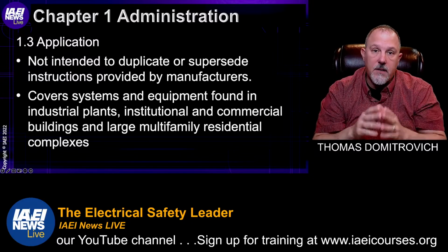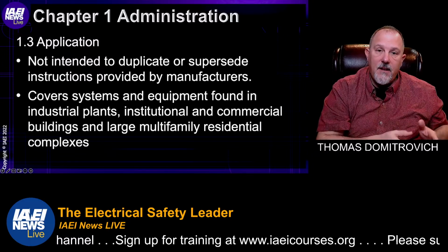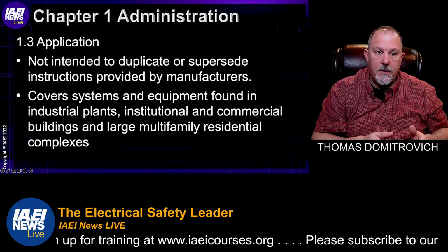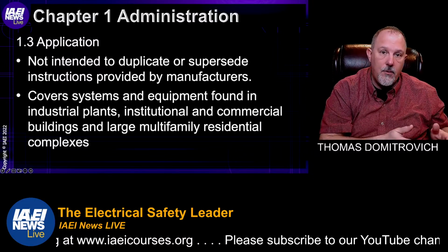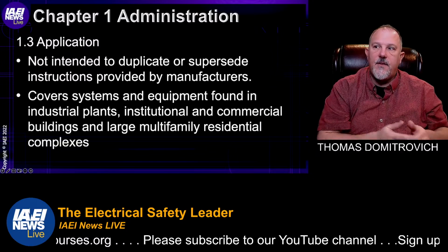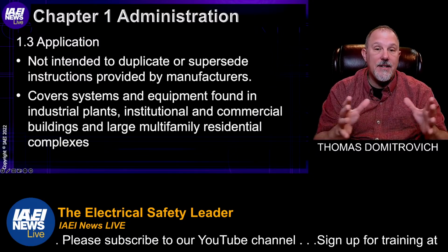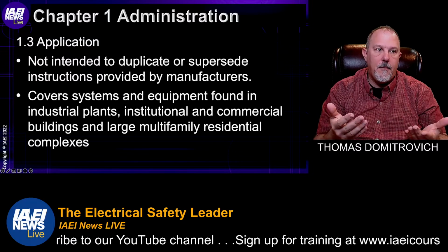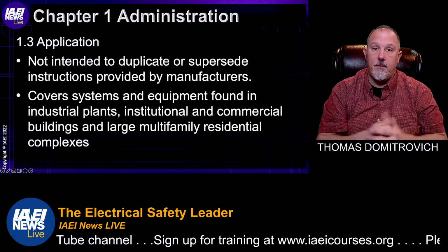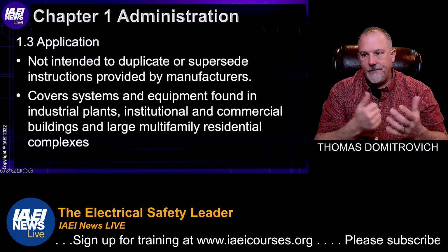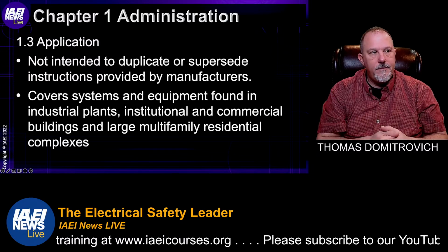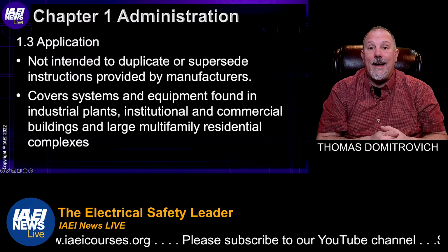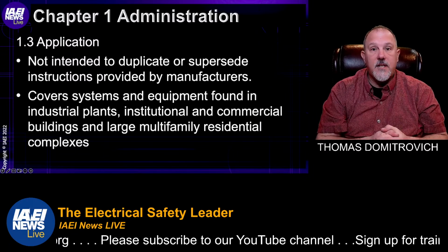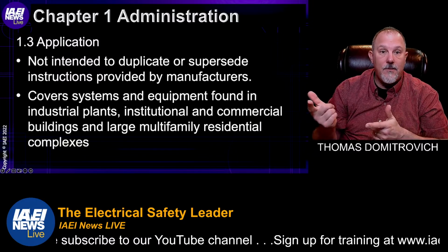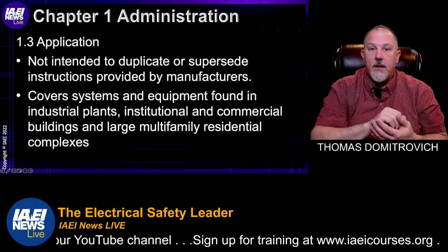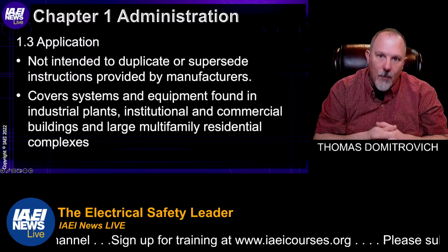That's a very important piece of the puzzle. If the manufacturer's instructions tell you to do something that 70B doesn't, you have to follow them. A gray area might arise if the manufacturer's instructions tell you to do something ridiculous, like wax the outside of the panel board once every 3 years, and that's not in 70B. Well, you'd have to do that because the manufacturer tells you to.